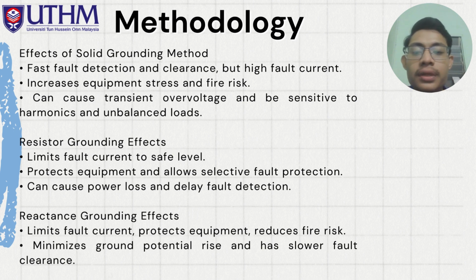On this slide, I will explain the effects of the neutral grounding methods. First is the effect of the solid grounding method. It has fast fault detection and clearance, but high fault current. It increases equipment stress and fire risk, can cause transient overvoltage, and is sensitive to harmonics and unbalanced loads. The second is resistor grounding effects. It limits the fault current to a safe level, protects equipment, allows selective fault protection, and can cause power loss and delayed fault detection. The third is the reactance grounding effect. It limits fault current, protects equipment, and reduces fire risk. It also minimizes ground potential rise and has slower fault clearance.